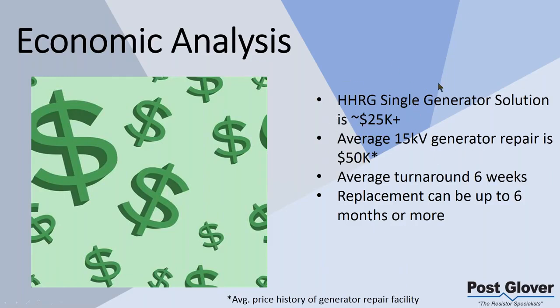This is a general number. I just want to do a very brief economic analysis of what it could look like for your HRG solution. If you have a single generator solution, we're looking at roughly $25,000. It could be a little more depending on your options. If you have a zigzag, all these things could drastically increase the price. But generally speaking, if you have what I showed you, we're roughly looking at about $15,000 to $70,000 more than your average low resistance ground for that same voltage. Let's assume a 15 kV solution.